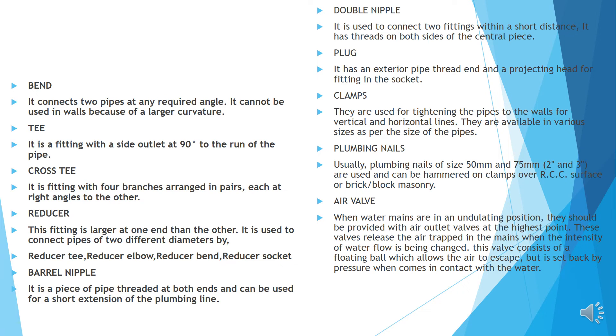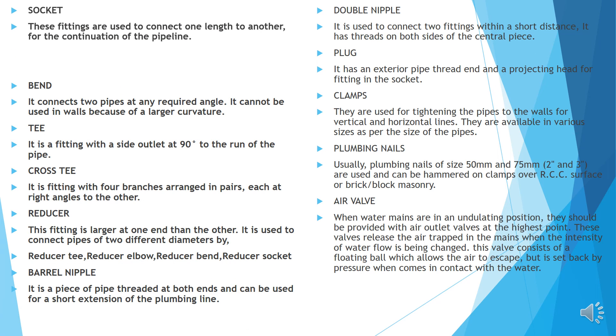Plug: it has an exterior pipe thread and a projecting head for fittings at the socket. Clamps: used for tightening pipes to the walls for vertical and horizontal lines; available in various sizes. Plumbing nails: usually sizes 50 to 75 mm, can be hammered for a clamp over RCC. Air valve: when water mains are in undulating position, they should be provided with an air outlet valve at the highest point. These valves release air trapped in the mains when the intensity of water flow changes. The valve consists of a floating ball which allows the air to escape but is set back by pressure when it comes into contact with the water. Socket: used to connect one length to another for continuation of the pipe. Elbow: connects two pipes at 90 degrees and has a short extension.